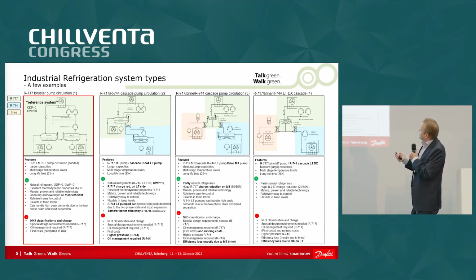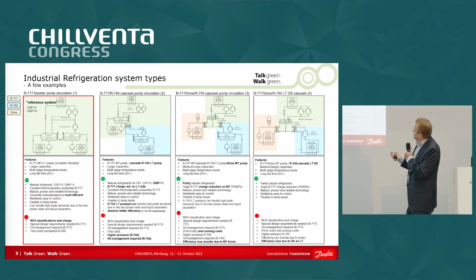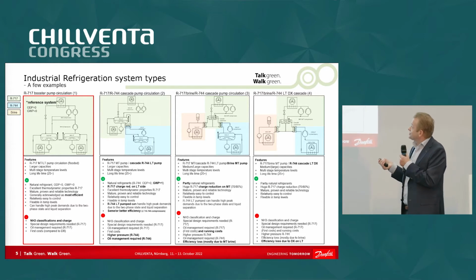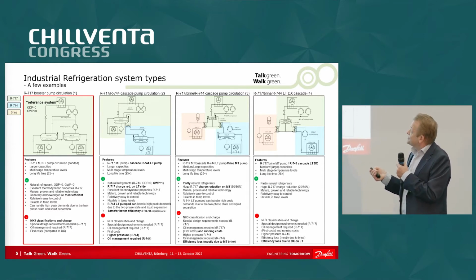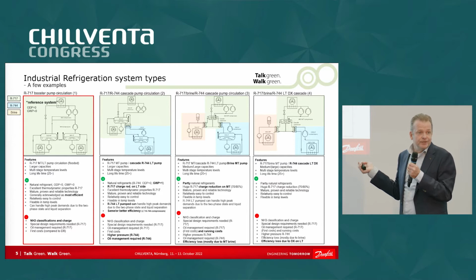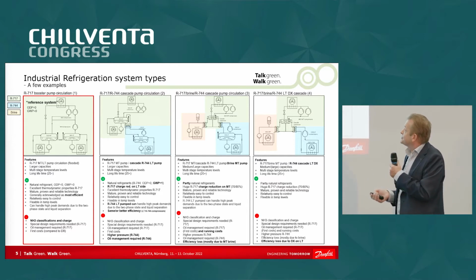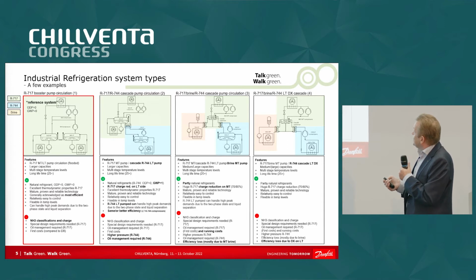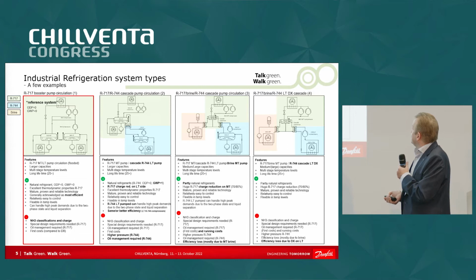The second way is, say, I keep the ammonia on top, I keep the low temperature here, and I change the ammonia part into brine. It's a very simple way of reducing the charge, but you could say the efficiency, what happens here, because now we have two heat exchangers in the system, and of course a heat exchanger reduces the efficiency. But the good thing is you can really reduce the charge, like 70 to 80%, which is good. But of course, the running costs are higher because the majority, this one here, is simply not as effective as ammonia or CO2.